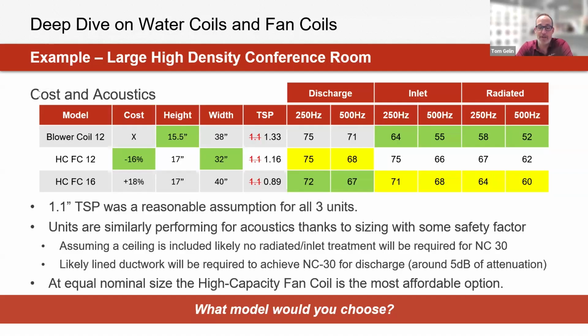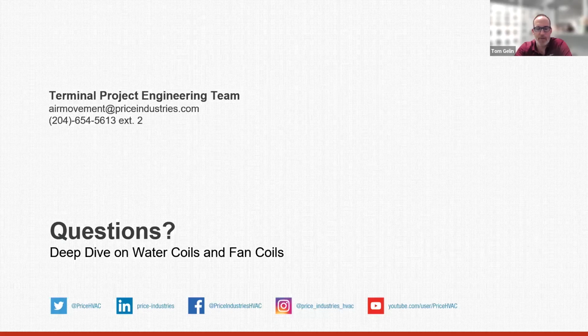So there's a lot there, as you know, because we did do a fairly deep dive into fan coils and coils. And not necessarily any right or wrong answer, but Tom alluded to it too. Likely it would be the second option, or HCFC12, lower cost, but relatively being able to be within the ideal acoustics range at a little bit smaller of a footprint for achieving the same results. But again, it just shows that there are different potential solutions, whether it be a blower coil or fan coil, for laying out these systems. I think fan coils are inherently problematic for sound because there's usually no flex on them. Yeah, and flex solves a lot of problems acoustically.